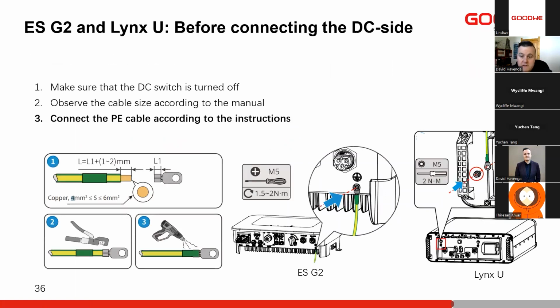We're going through the connections of the inverter. It is very important to install correct grounding on the inverters. Low voltage battery inverters aren't as susceptible to interruptions when grounding is not there, but it can cause a failure of the device because the cabinet and all of that can build up induction. That induction can lead to issues down the line.